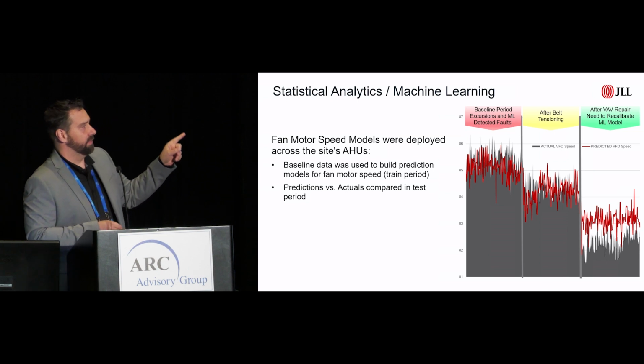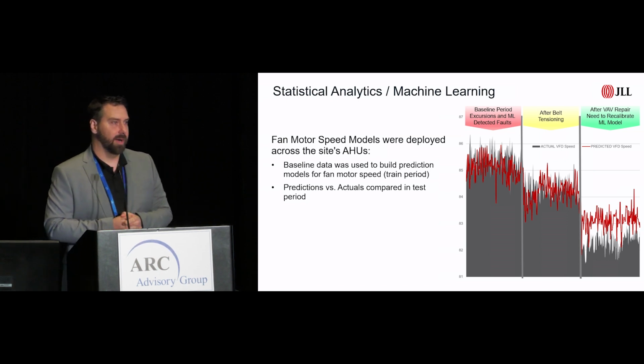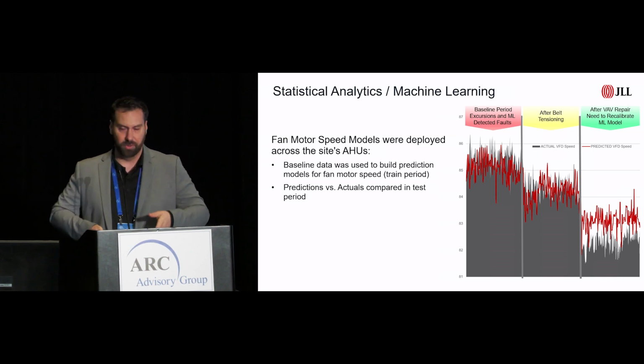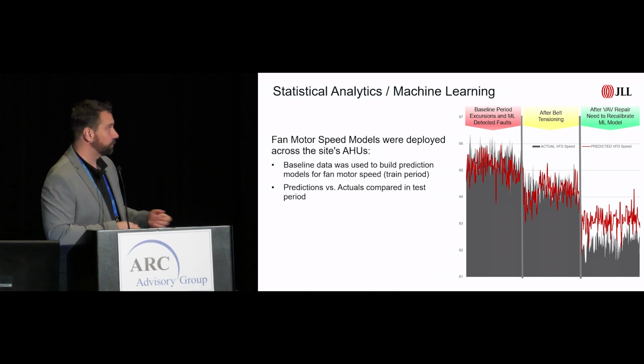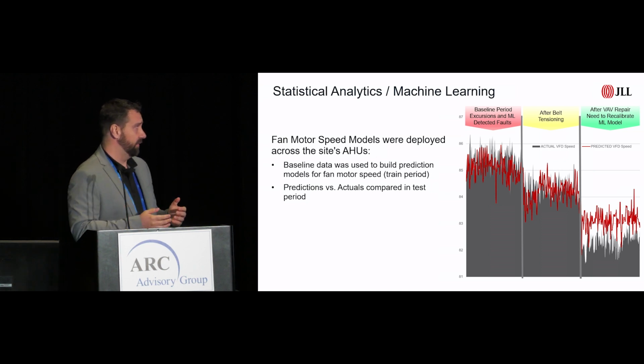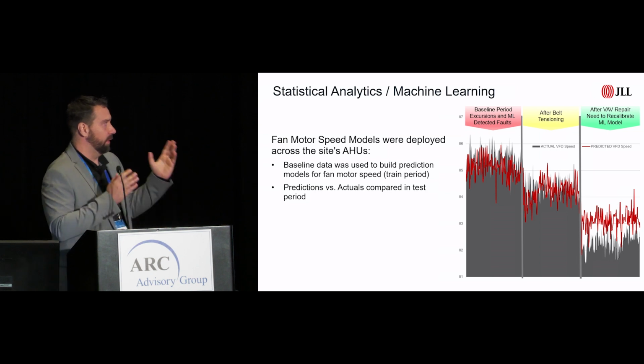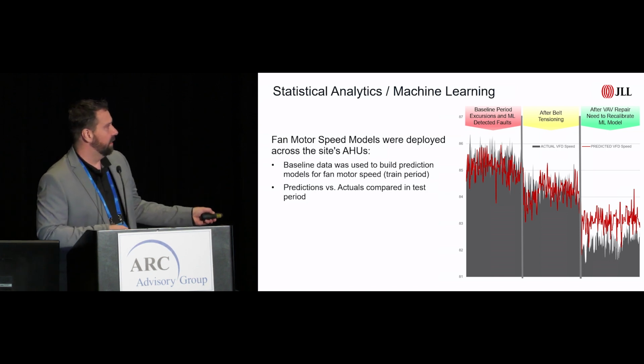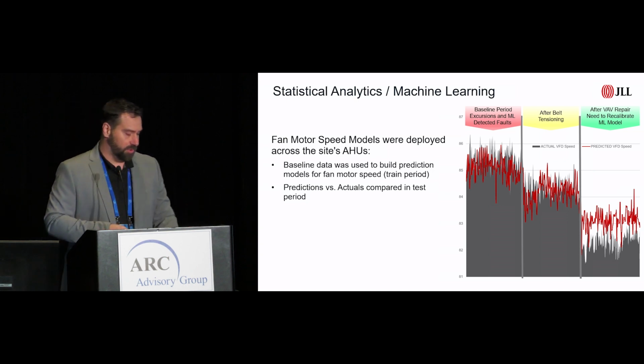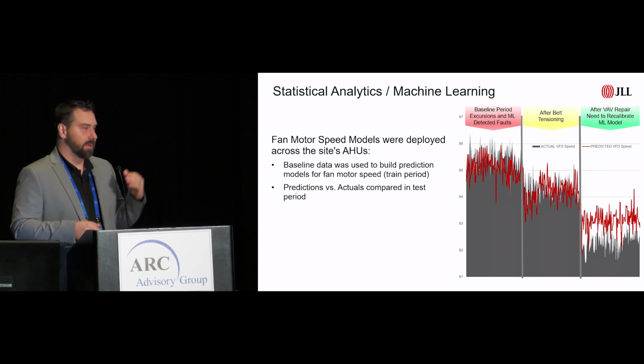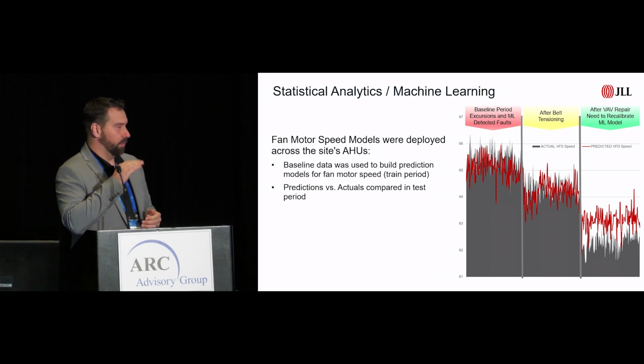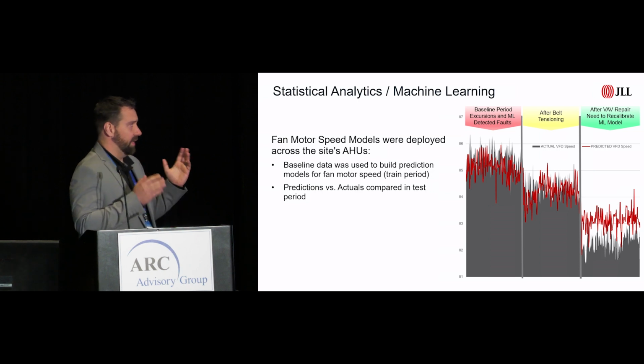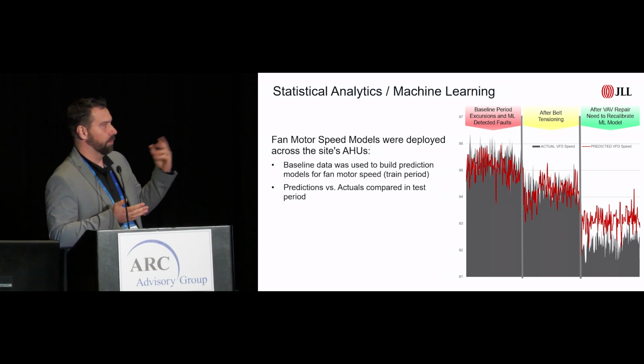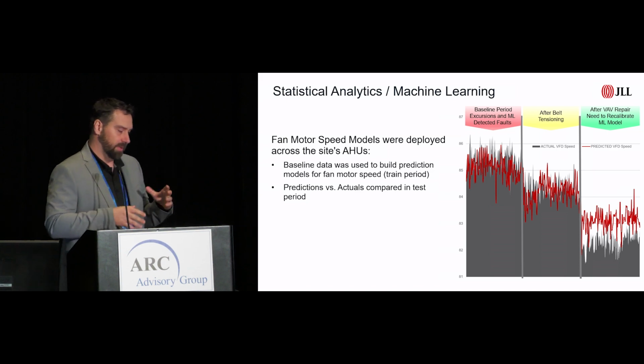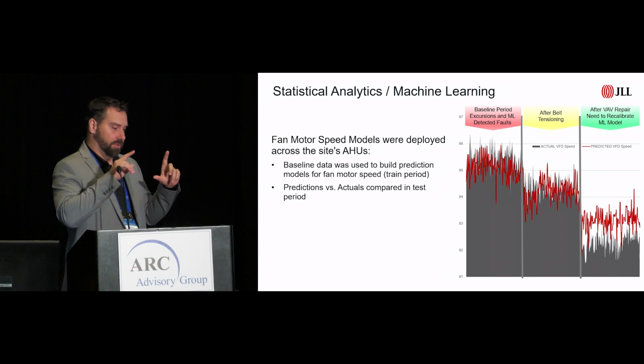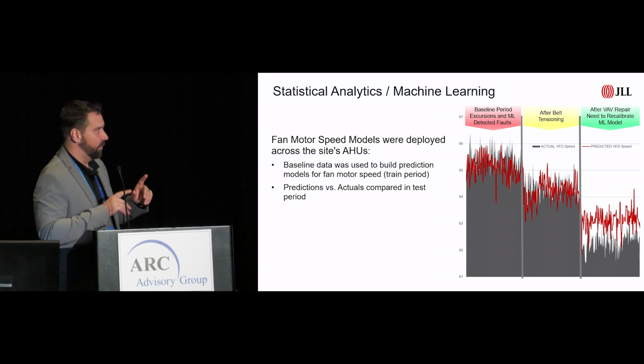That red line is the system's understanding of what would be required from the fan, the VFD capacity, 0 to 100%. How hard would that fan need to work? The gray is the actual output of that fan. So when we turned it on, that's what we got immediately, right? And then just using the vibration information, looking at this screen, you would say, all right, we're in line with what the system thinks it should be going through versus what we actually had. So our system is looking at the real world operational demand of the system and assumes, with all of the criteria in it, this is what I think the fan should be doing. And if the gray matches the red, everybody thinks we're good and happy.